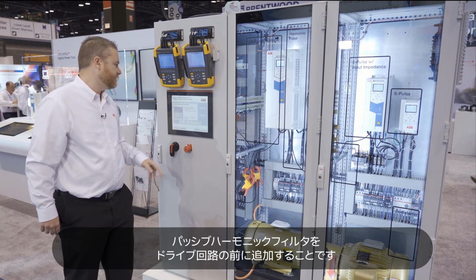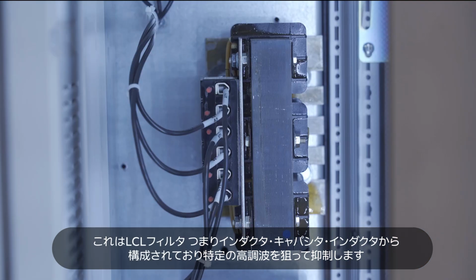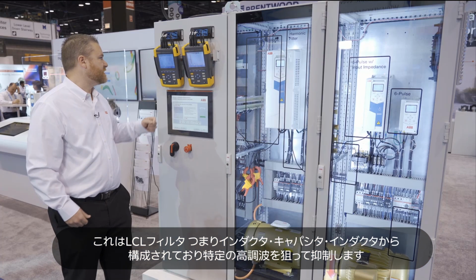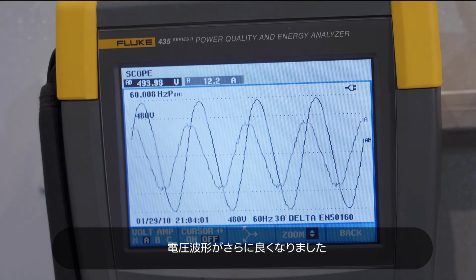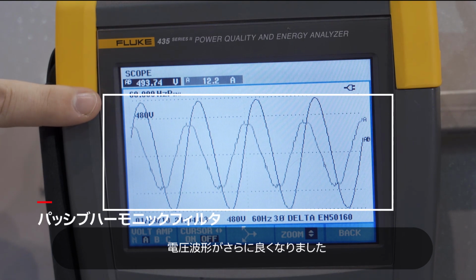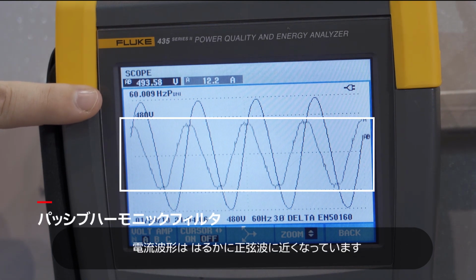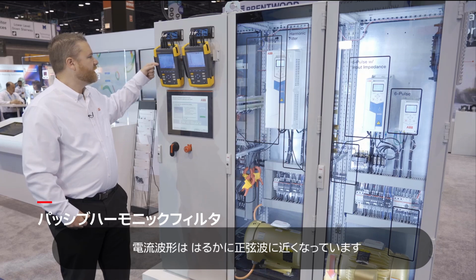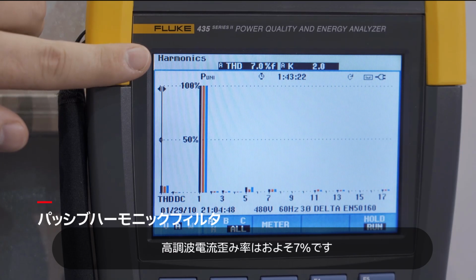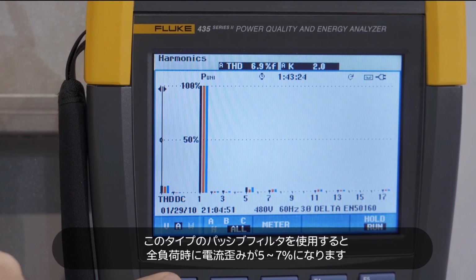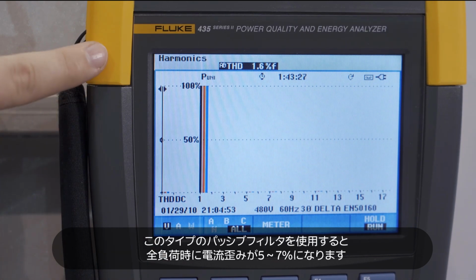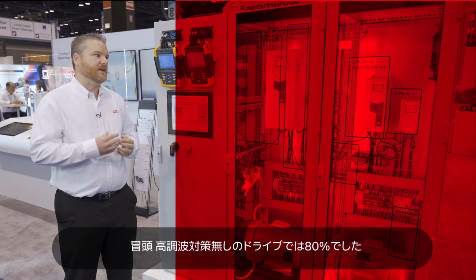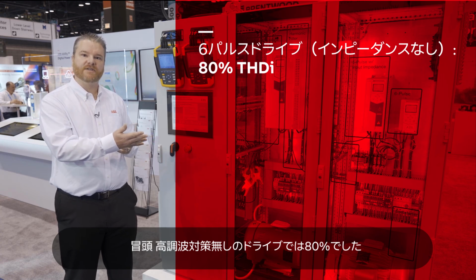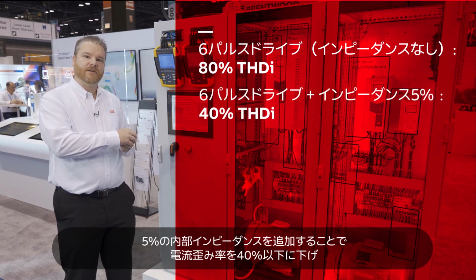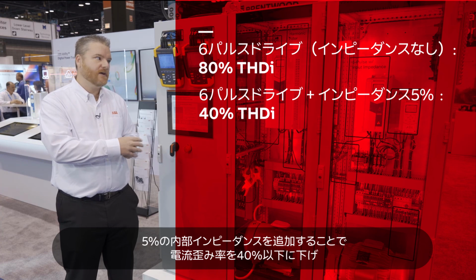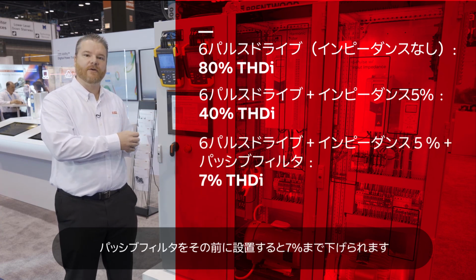Another way to reduce harmonics by not changing the drive technology itself is to add a harmonic filter in front of it. So this is an LCL, an inductor-capacitor-inductor harmonic filter, tuned specifically to go after certain harmonics. Now you can see that the voltage waveform is even better. The current waveform is much more sinusoidal. And I come over here and look at my harmonics, and it's roughly 7%. These types of filters will get you into that 5 to 7% current distortion when you're at full load. So when I started with that first drive with no harmonic mitigation, it was at 80%. Added the 5% internal impedance, that brought me down to less than 40. If I put a passive filter in front of it, that can get me down to 7%.